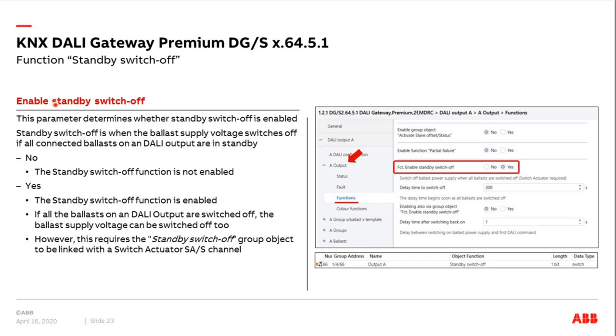Step by step: start in Output A, go to the submenu Functions. In the Functions menu, set 'Function Enable: Standby Switch-Off' to yes. The standby function will then be automatically activated if all ballasts are switched off. You will also get a group object — for example group object number 66 — called 'Output A Standby Switch-Off'. This is a one-bit group object: the gateway sends the value 0 or 1 to switch the supply voltage via the switch actuator.